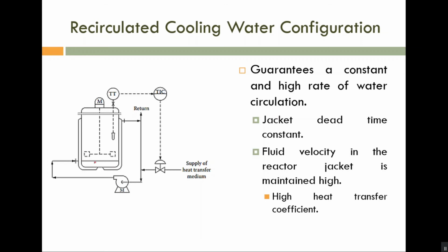So at least we can consider the extreme points. This one is the inlet point. Here we have minimum temperature because this one is coolant, and this one is the outlet side, and here we can expect large temperature. Okay, so now we have to reduce the effect of these two different temperatures, which make the temperature control inaccurate. Okay, an offset is created.